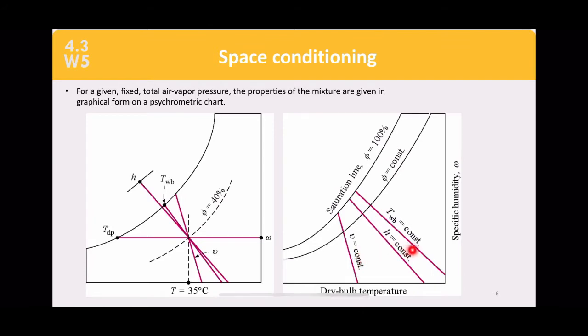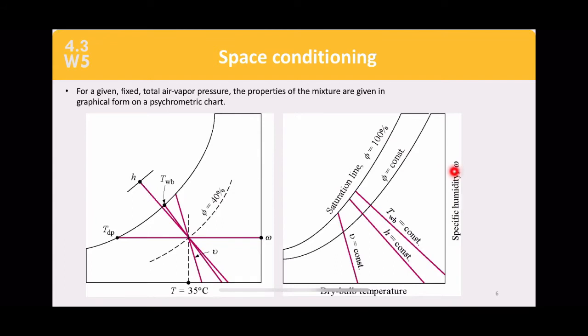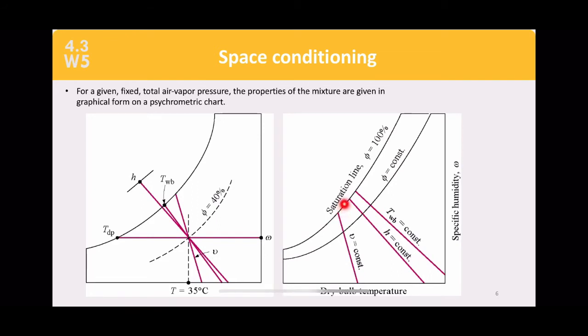The lines involved in the psychrometric chart include: specific humidity omega (in kilograms of vapor per kilogram of dry air), specific volume constant lines, enthalpy constant lines, wet bulb temperature lines, and the saturation line where humidity reaches 100%. Dry bulb temperatures are shown along the bottom.